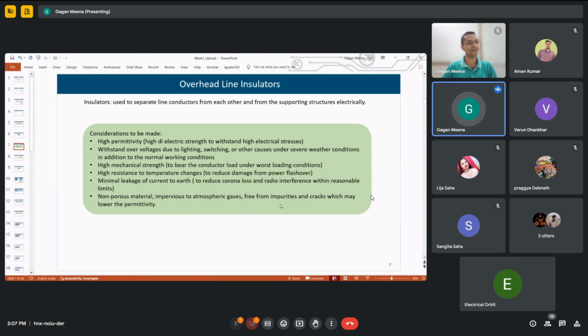Although these lightning strikes are there, they are of very short duration. So for short duration, these insulators, and even the lines, should be able to withstand that transient over voltage, lasting a few milliseconds or seconds. For that also they have to withstand the over voltages.